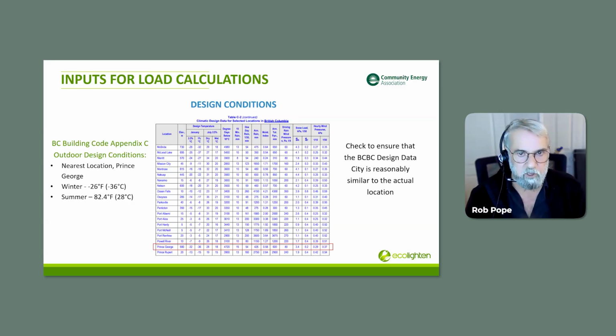It's pretty straightforward. We have to design to some conditions, so we design to an extreme of some sort. We're establishing an outdoor condition in the summer - the hottest days, the 2.5%, and the winter coldest days - not the absolute coldest, but a percentage.